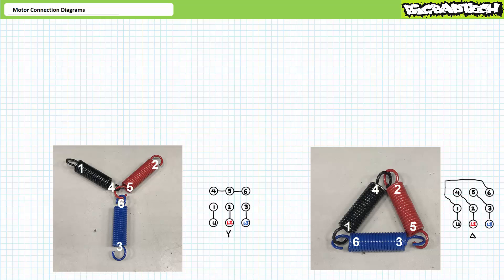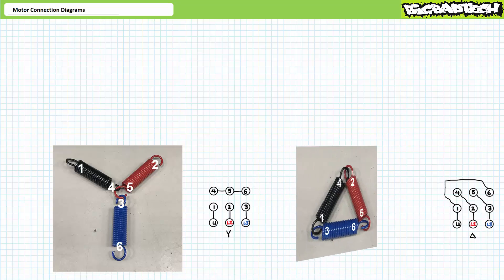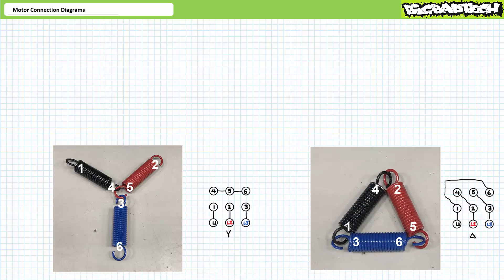Consider the following subtle modifications and their not-so-subtle consequences. Consider a Y-configured motor with leads 4, 5, and 3 forming the central node of the Y. It's still three windings in a Y configuration, but this won't work — winding 3-6 is flip-flopped. Similarly, consider a delta-configured motor going 1, 4, 2, 5, 6, 3 in a clockwise fashion. It's still three windings in a delta configuration, but this won't work; winding 3-6 is again flip-flopped. Current direction influences magnetic polarity, so connected in this improper fashion, winding 3-6 would be a north when it's supposed to be a south and vice versa, hopelessly wrecking any chance of establishing a smoothly rotating magnetic field in the stator. Follow the connection diagrams exactly as illustrated.